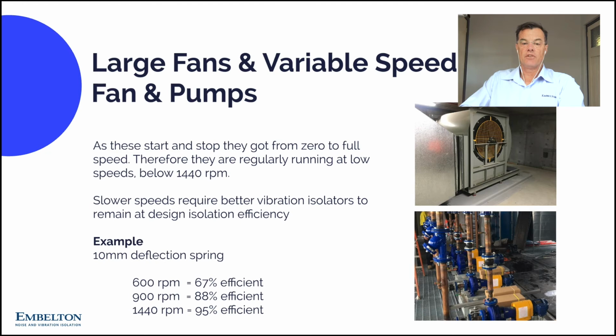Large fans and variable speed fans and pumps. As these start and stop, they go from 0 to full speed. They're regularly running at low speeds below 1440 RPM. Slower speeds require better vibration isolators to remain at the design isolation efficiency.